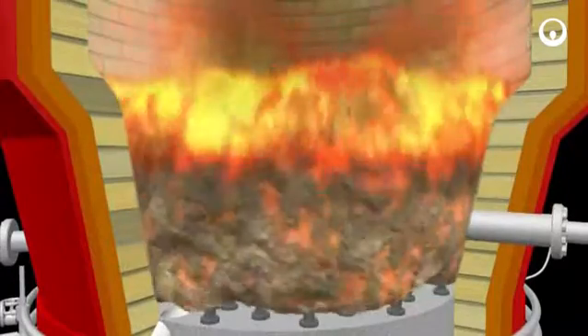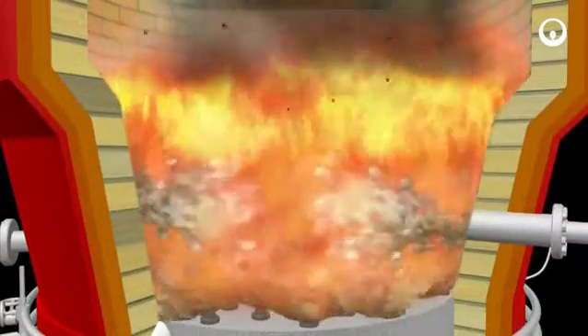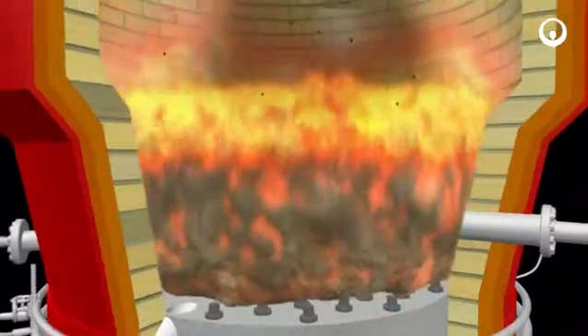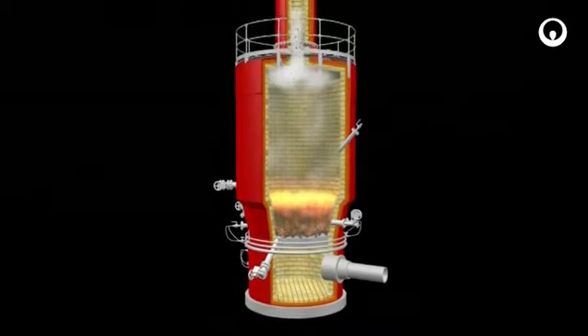This fluid creates turbulence in the sand bed. The sludge, having previously attained a dryness of 30 percent, is injected into the bed. Crushed by the sand, the sludge dries rapidly and enters into the combustion phase, which ends in the combustion chamber at a temperature of 850 degrees.